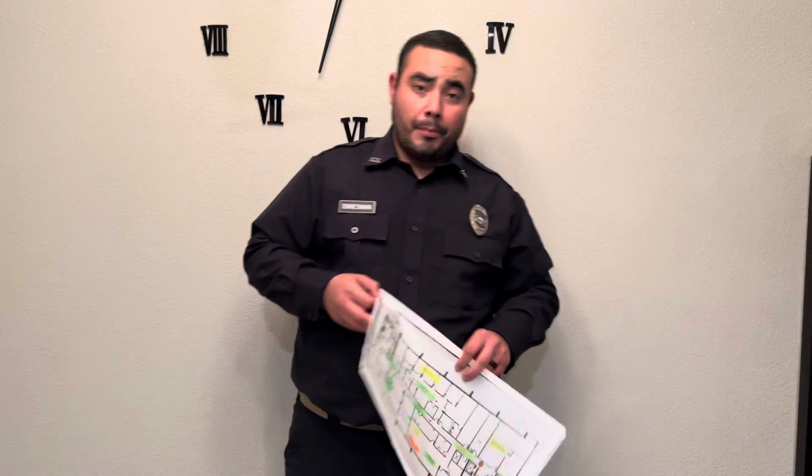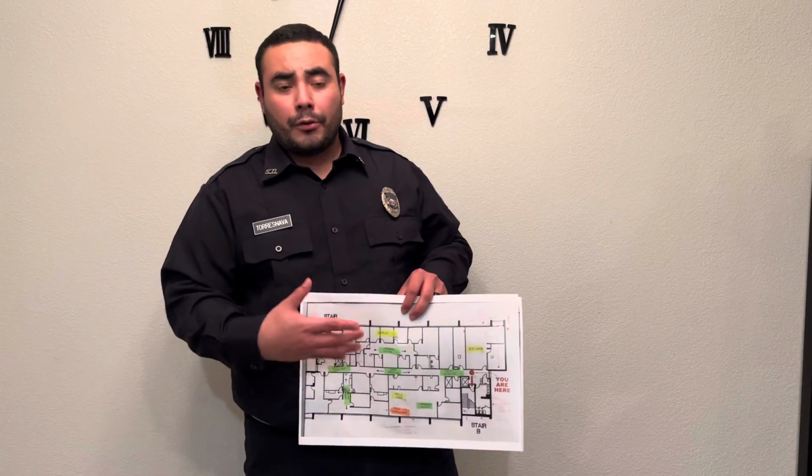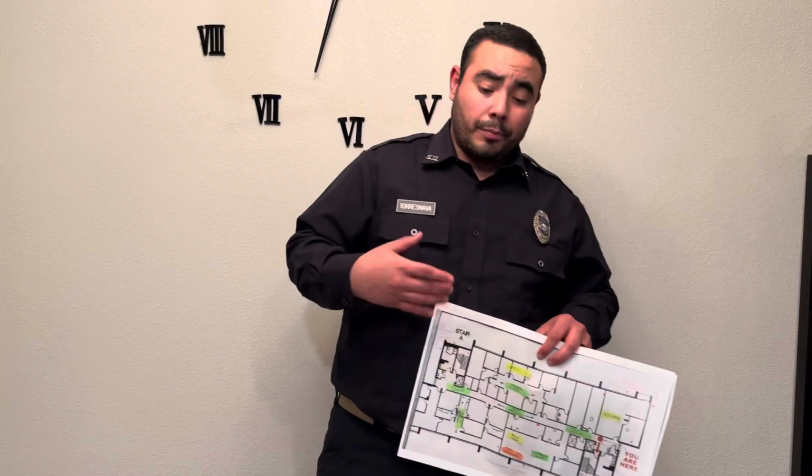It's amazing. Also, one thing that I forgot to mention is that we need the primary power supply that comes directly from the building, and our secondary or supplementary power supply, which is an external one, that must provide power to every single alarm and every single suppression fire alarm system. The reason why is because if the main power goes off, we still got the secondary power feeding our systems, meaning that even if it's a shutdown, they're going to still work and let you know that there's a fire.